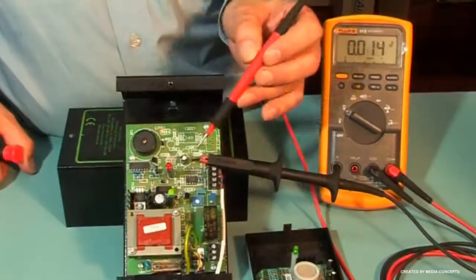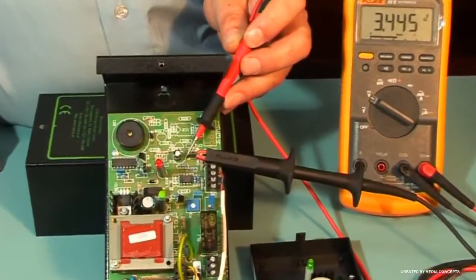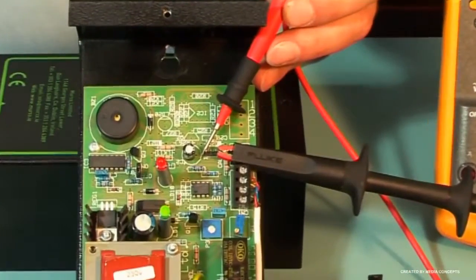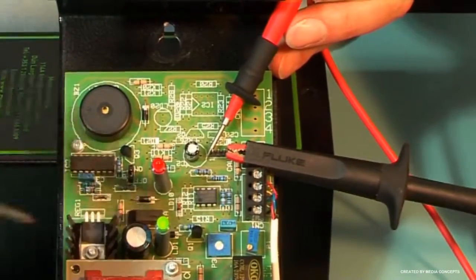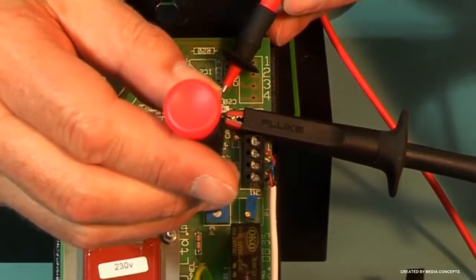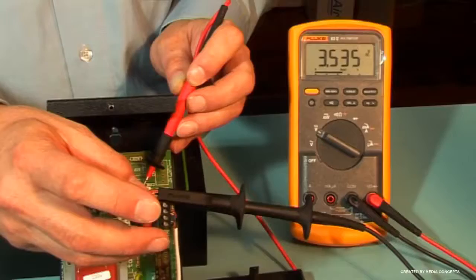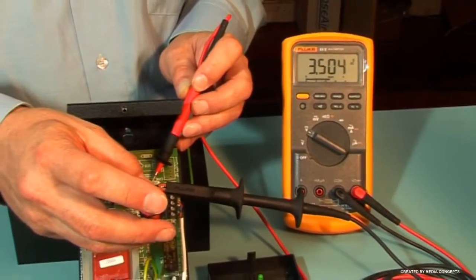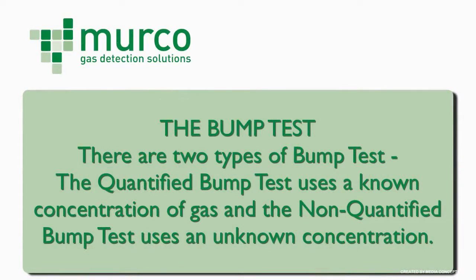Move the positive lead from pin 2 CN1 to pin 1 on the CAL header and adjust P3 to 3.5 volts or as per the alarm voltage as shown on the rating label. There are 2 types of bump test. The quantified bump test uses a known concentration of gas and the non-quantified bump test uses a non-known concentration.